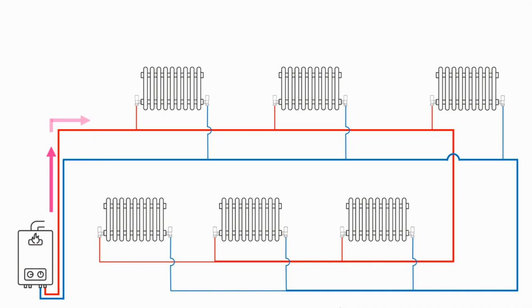What we're looking to achieve by balancing a heating system is that as the hot water leaves the boiler and approaches the T for any particular radiator, there's no greater or lesser resistance for the flow to go either through the radiator or to carry on in the flow to fulfill the heating requirements of the other radiators downstream on the circuit. This way we're ensuring that all of the radiators on the system are getting sufficient amounts of hot water to achieve their heat output.